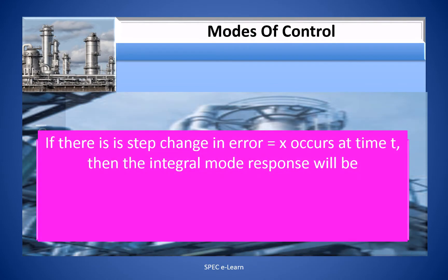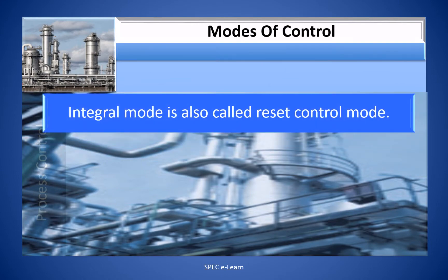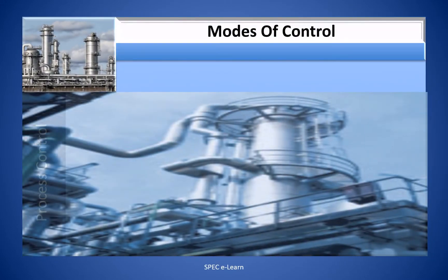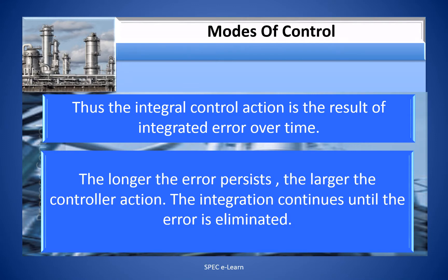If there is a step change in error equal to x occurring at time t, then the integral mode response will be MV = Kc·x / Ti. The integral mode is also called reset control mode. When error is detected, the controller responds by taking a proportional action first. Since the PV has still not come back to set point, the controller will continue to send output to the control valve until the error is eliminated. This integral control action is a result of integrated error over time — the longer the error persists, the larger the control action. The integration continues until the error is eliminated.